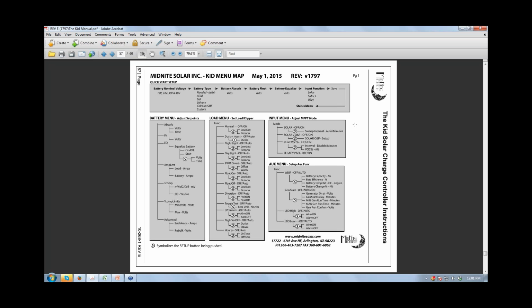The people that were installing the systems for us, on the DIN rail mount, they were using these breakaway fuses that you can just pop up, and you can turn off the system to the load or to the battery. A lot of times when we disconnect and reconnect the loads, sometimes the MidNite Solar would shut off and stay off for a while. Is that typical?